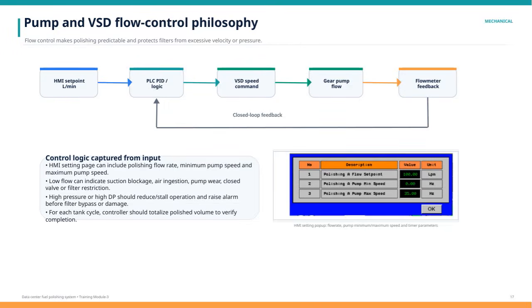This slide focuses on the pump and variable speed drive, or VSD, flow control philosophy used in fuel polishing systems. The core idea here is to make the flow control predictable, which helps protect the filters from damage caused by excessive velocity or pressure. At the heart of this system, the operator uses the HMI, or human-machine interface, to set flow rate parameters in liters per minute, as well as minimum and maximum pump speeds. This input serves as the set point for the system. From the HMI set point, the PLC, the programmable logic controller, uses PID control logic to generate a speed command for the VSD. This command adjusts the gear pump flow, and the flow meter provides real-time feedback to the PLC.